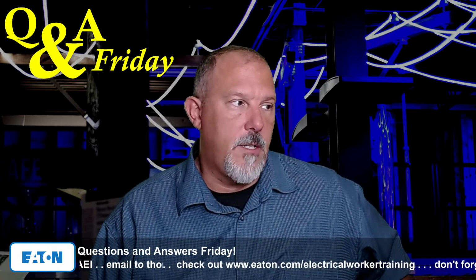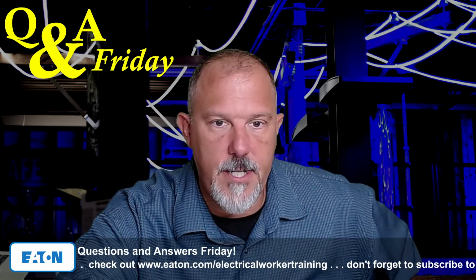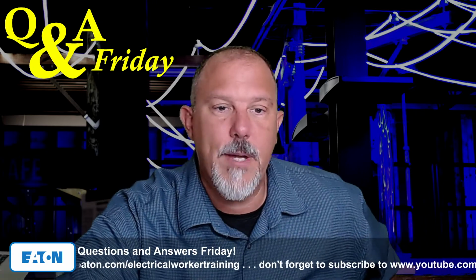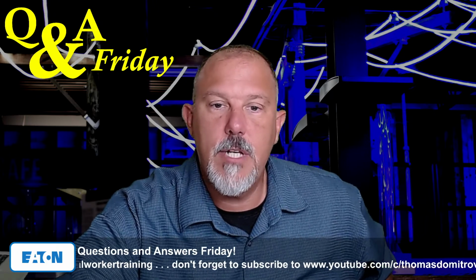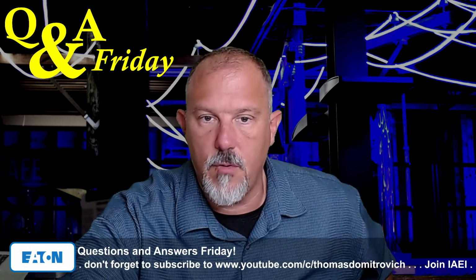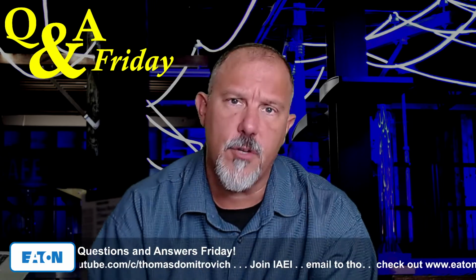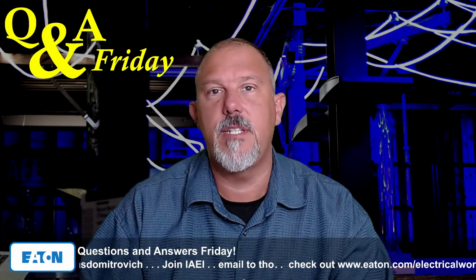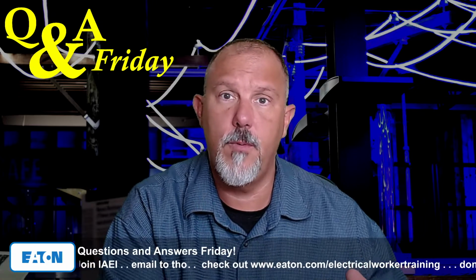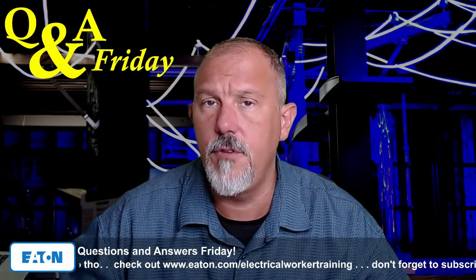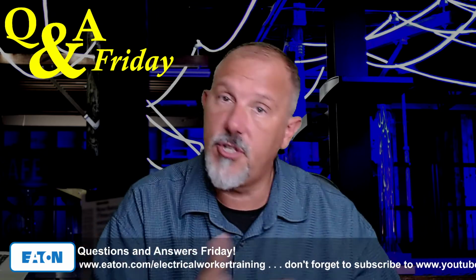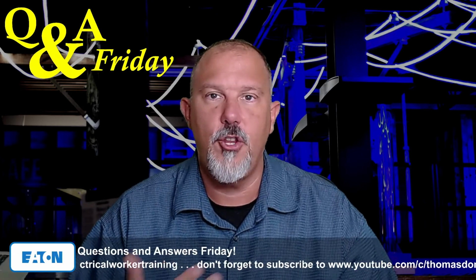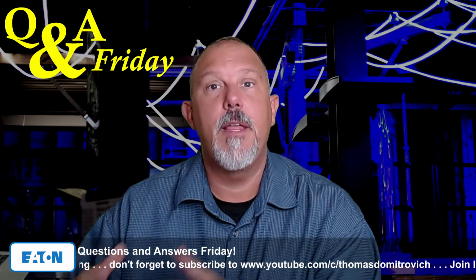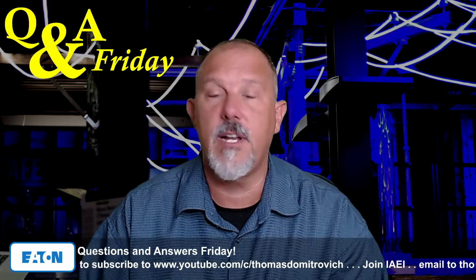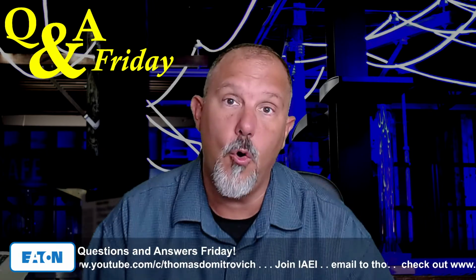And now JW had another comment on the 90 degree and 105 degree things too. Low voltage breakers have thermal heating units that can actually be heated to nuisance trip due to heat of the conductors. Medium voltage equipment using things like current transformers isn't subject to the same heat from the conductors. All right. That's a good point. And when you get into medium voltage applications, I think what you're talking about are the 75 degrees C, the 80% versus 100% rated with regard to 100% of the ampacity, not having to do the 1.25 multiplier. You are right. When you land conductors, you're still landing them on a circuit breaker, but there's no thermal element. You're basically tripping that breaker based upon a relay that is monitoring CTs and PTs and deciding when to tell the switch, so to speak, to open.